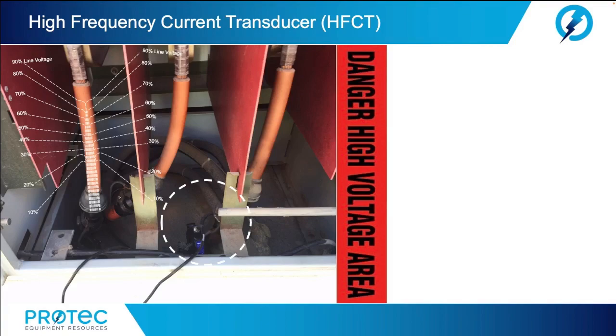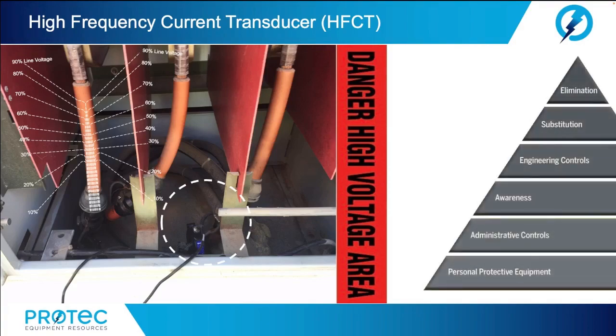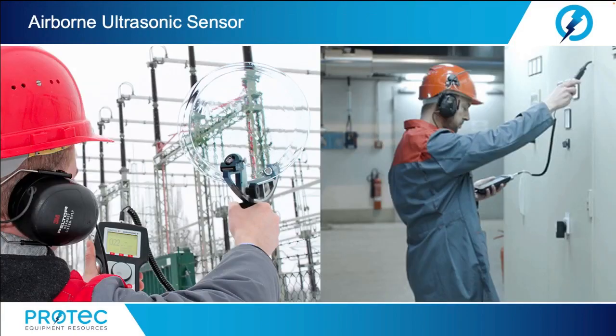So, the challenge in performing the online partial discharge test on energized electrical power cables is getting the high-frequency CT connected safely. Perhaps the best solution is to use the engineering controls from the hierarchy of risk control methods. One engineered approach would be to pre-install the high-frequency CTs into the cable landing compartments. The coax cables can be safely routed along the inner panels of the compartment and then brought out through a bulkhead adapter. Testing can then be carried out safely at any time by simply connecting the scanning equipment to the test connector on the bulkhead adapter. Another approach might be to bring the cable shields out of the cable landing compartment.